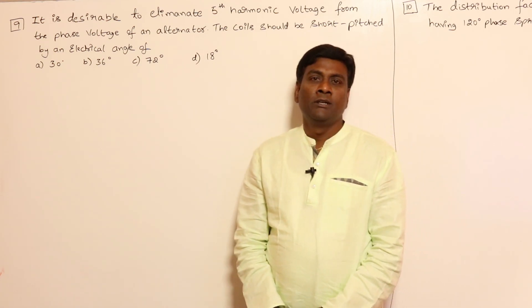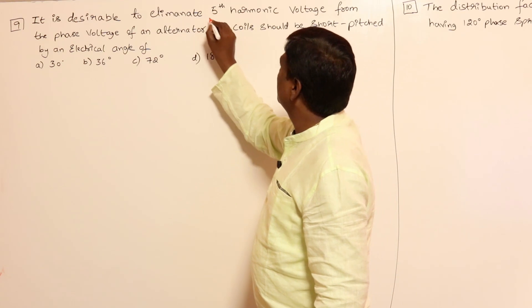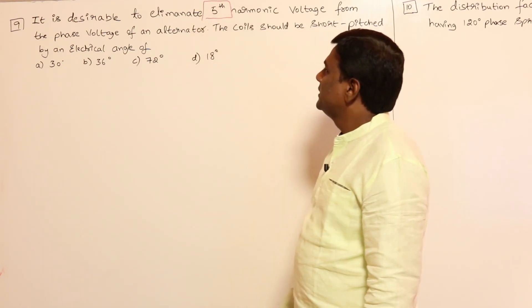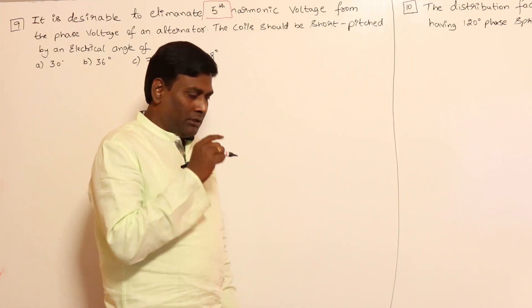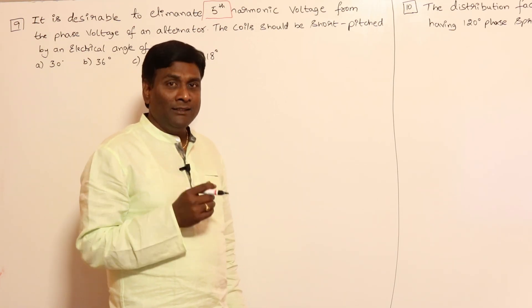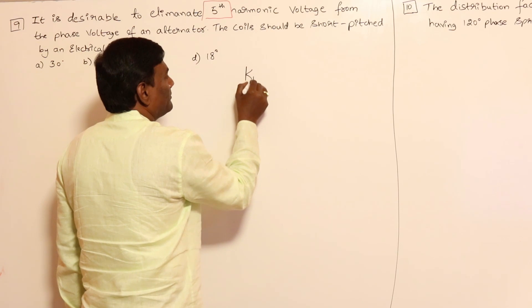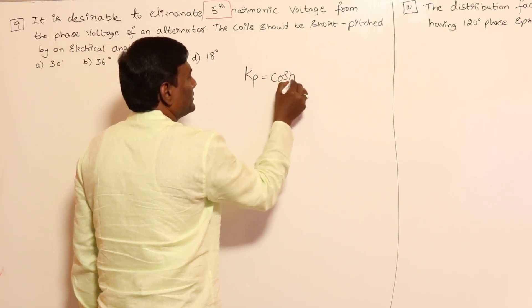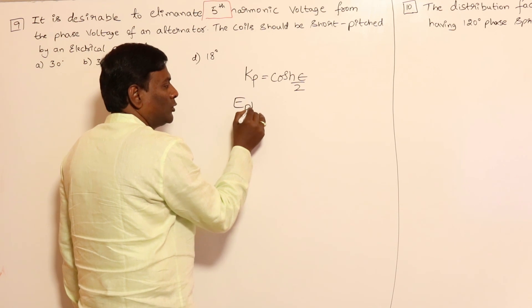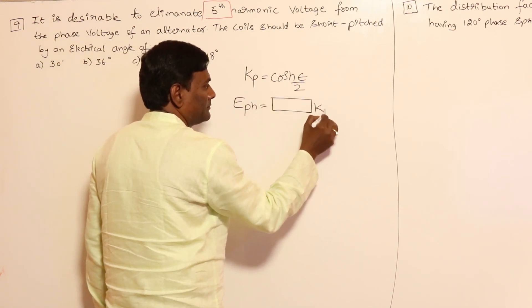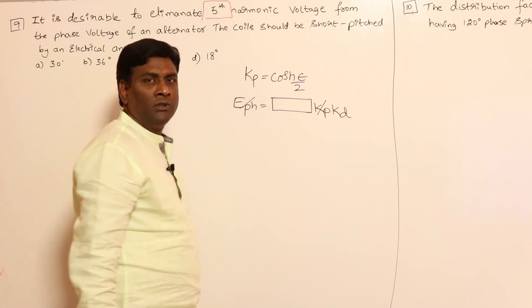In this session, let us take two more problems on alternators at no-load conditions. It is desirable to eliminate the fifth harmonic voltage from the phase voltage of an alternator. The coil should be short-pitched by an electrical angle. In the pitch factor discussion, we covered how to eliminate any harmonic component. The pitch factor kp equals cos(hε/2), and the total induced voltage per phase includes the factor kp × kd. If kp becomes zero, that harmonic component is eliminated.